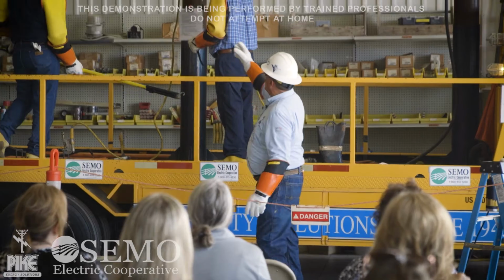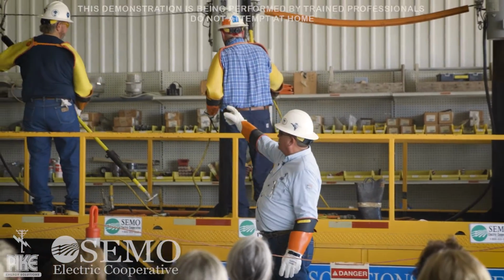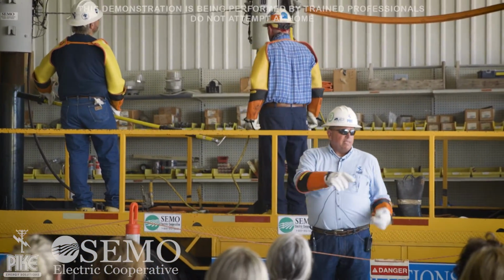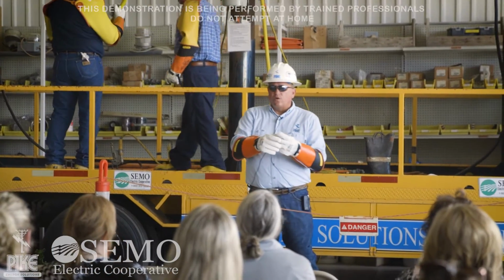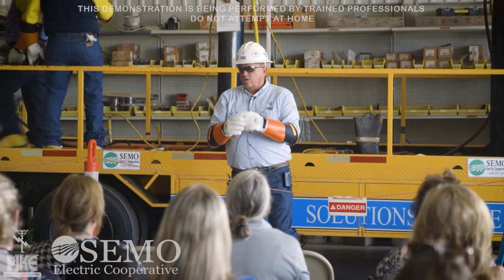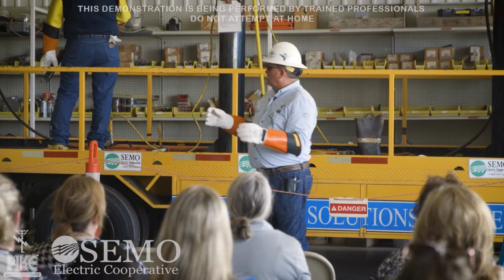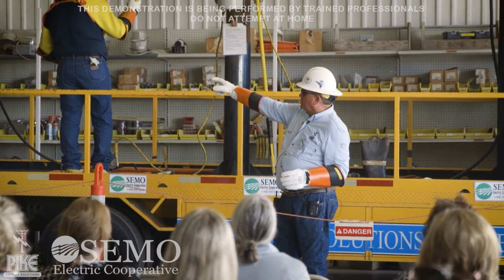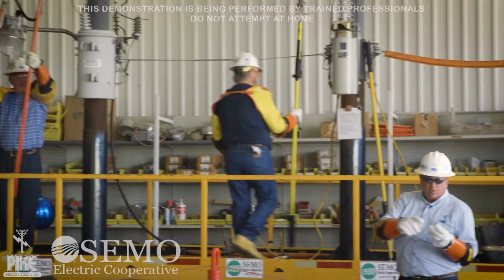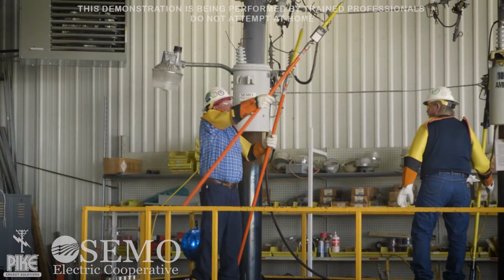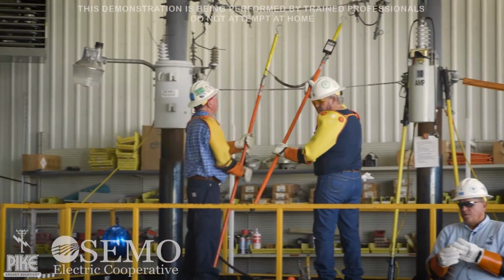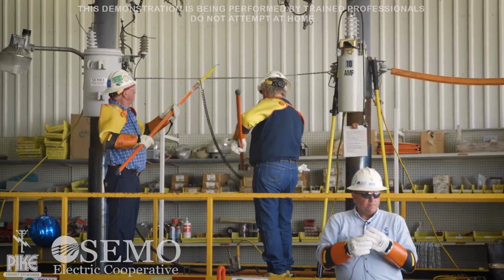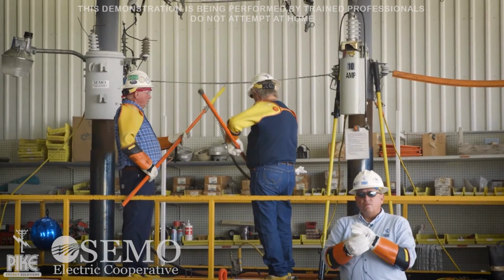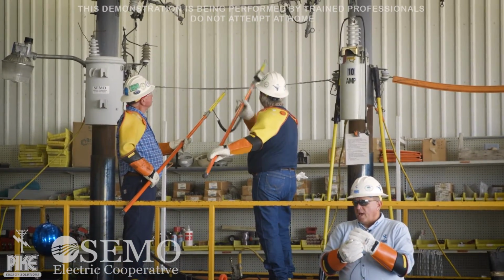So that's what they did here. They take the reclosers offline. The second thing we do is test the line. We test it for absence of voltage. We're looking for 0. So Willis is getting his phasing sticks here. They're going to check, make sure there's no voltage on the line. And the third thing we do is ground the line. Then the last thing we do is flag and tag.